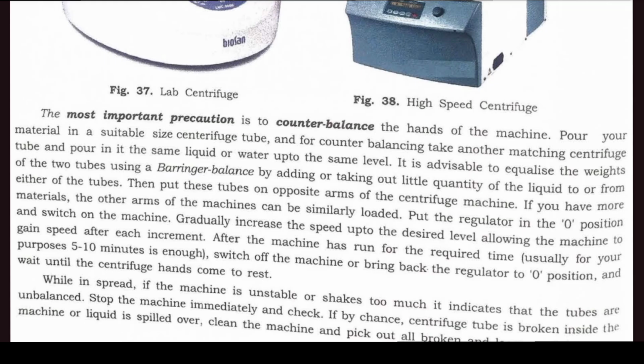The most important precaution is to counterbalance the arms of the machine. Pour your material in a suitable size centrifuge tube and for counterbalancing take another matching centrifuge tube and pour in it the same liquid or water up to the same level. It is advised to equalize the weight of the two tubes using a balance by adding or taking out little quantity of the liquid to or from either of the tubes. Then put these tubes on opposite arms of the centrifuge machine. If you have more materials, the other arms of the machine can be similarly loaded.